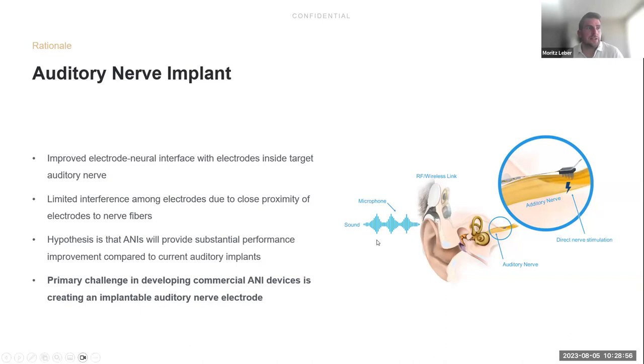Our effort is to replace the electrode array from conventional cochlear implants with our microelectrode array that has very, very small contacts - as an order of magnitude to compare, our electrode contacts are just a fraction in size compared to the diameter of a human hair, about 5 to 10 times smaller.